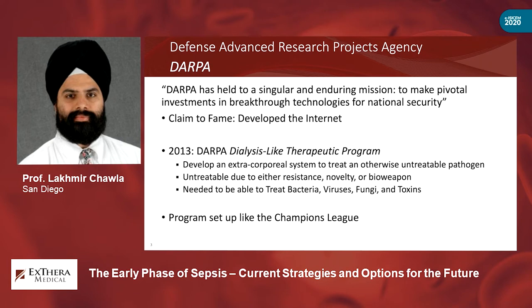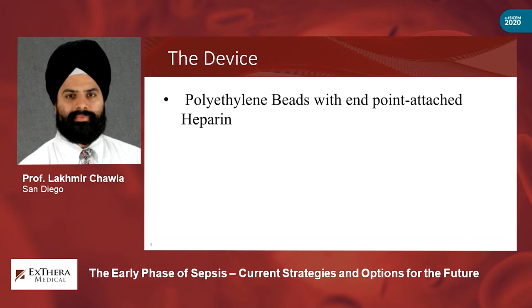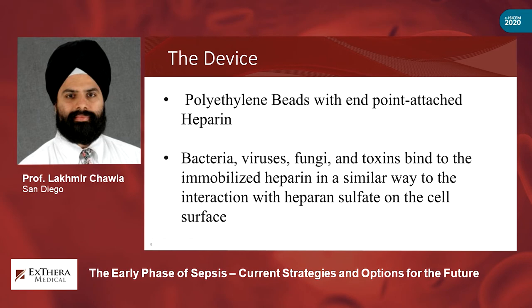The device that won this dialysis-like therapeutic program to remove bacteria, viruses, fungi, and toxins is the Seraph 100, made by ExThera Medical. That was in 2013. The device is now CE-marked and available in Europe, and it's also approved for COVID in the U.S. under an emergency use authorization. Essentially, it uses polyethylene beads with endpoint-attached heparin. It turns out that immobilized heparin binds bacteria, viruses, fungi, and toxins in a very similar way to heparan sulfate in mammalian tissue.